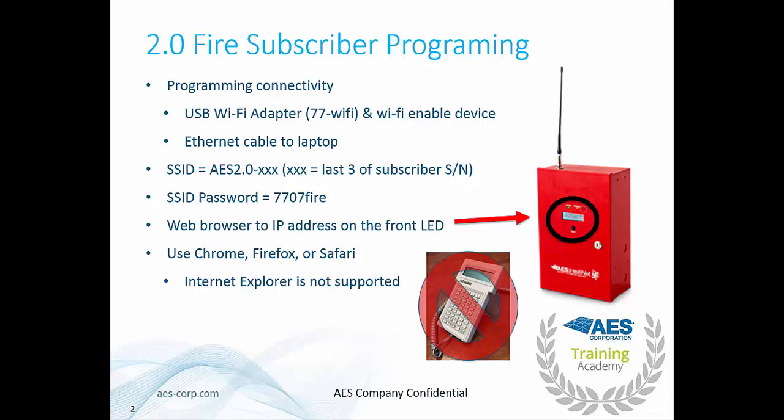You can also use an Ethernet cable with a laptop. If you are going to connect via Wi-Fi, plug in the USB dongle and then look for a Wi-Fi network called AES 2.0 dash the last three digits of the serial number of the device. You can find this by looking at the LCD screen on the front or there should be a sticker that has the serial number on the subscriber. Select this Wi-Fi network and if you're working with Windows 10 laptop note that you need to click the link where it says use passphrase. Then you will enter 7707 Fire. This is a hard coded password for all of our subscribers and that will give you access to the subscriber programming.